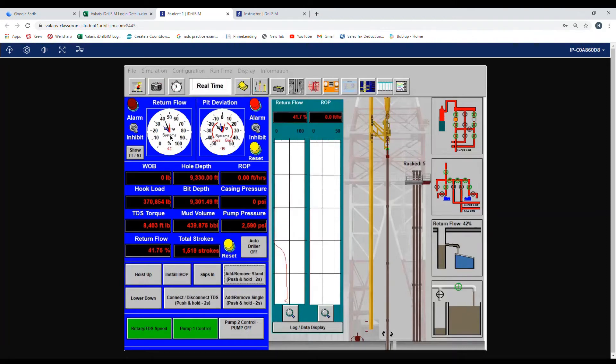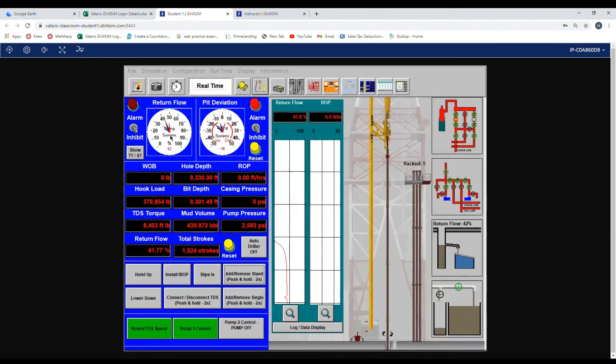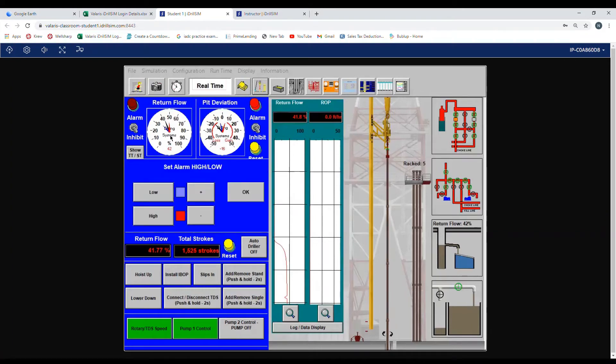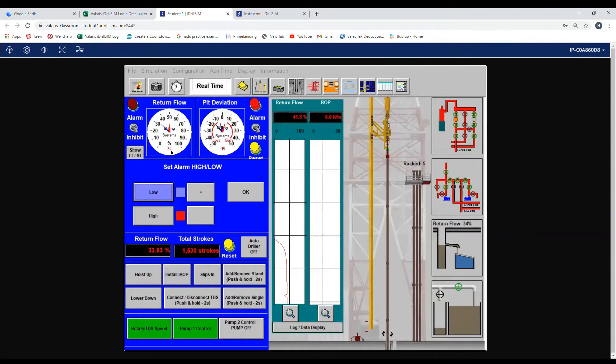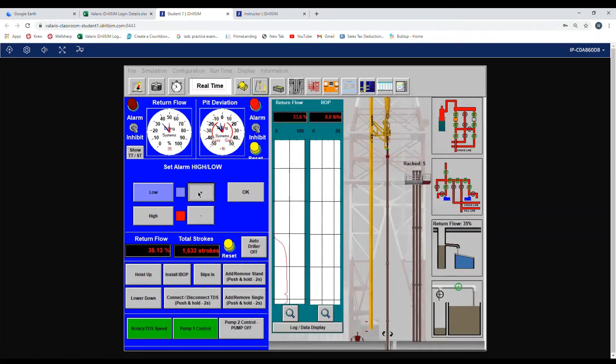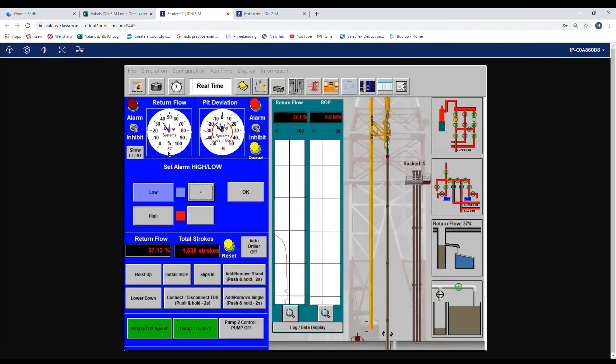Now we want to set our low alarm for 5 less than 42, so that is 37. We click back on the low box, we see it goes to 34. We press and hold the increase button until it comes to 37. Once it is 37 we press OK.